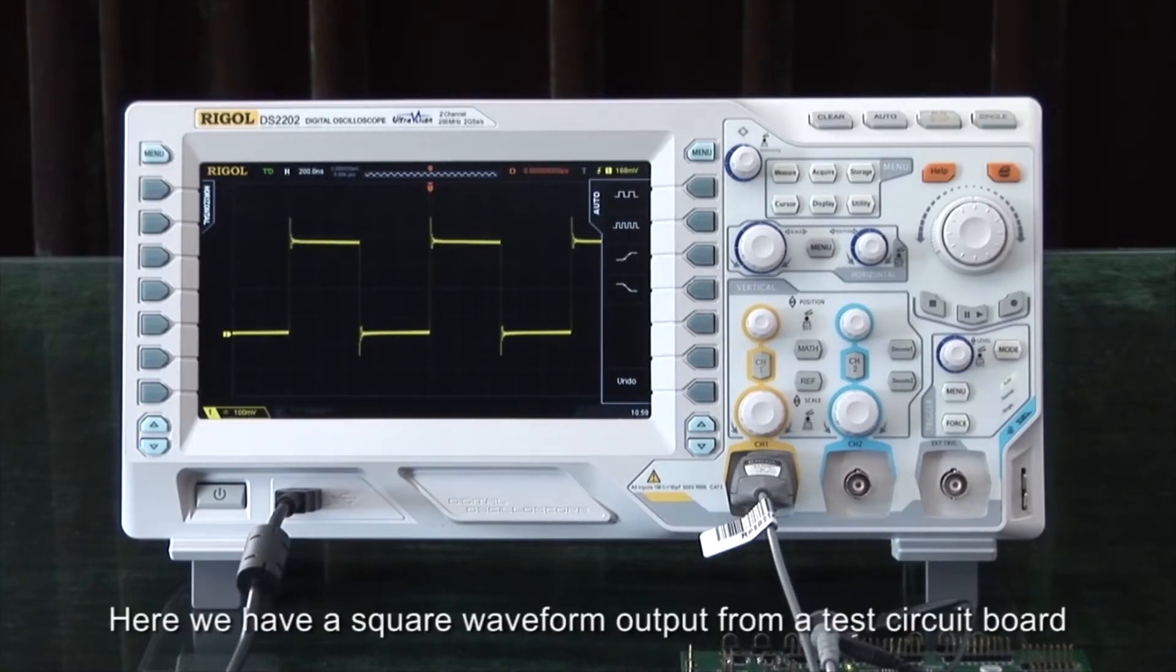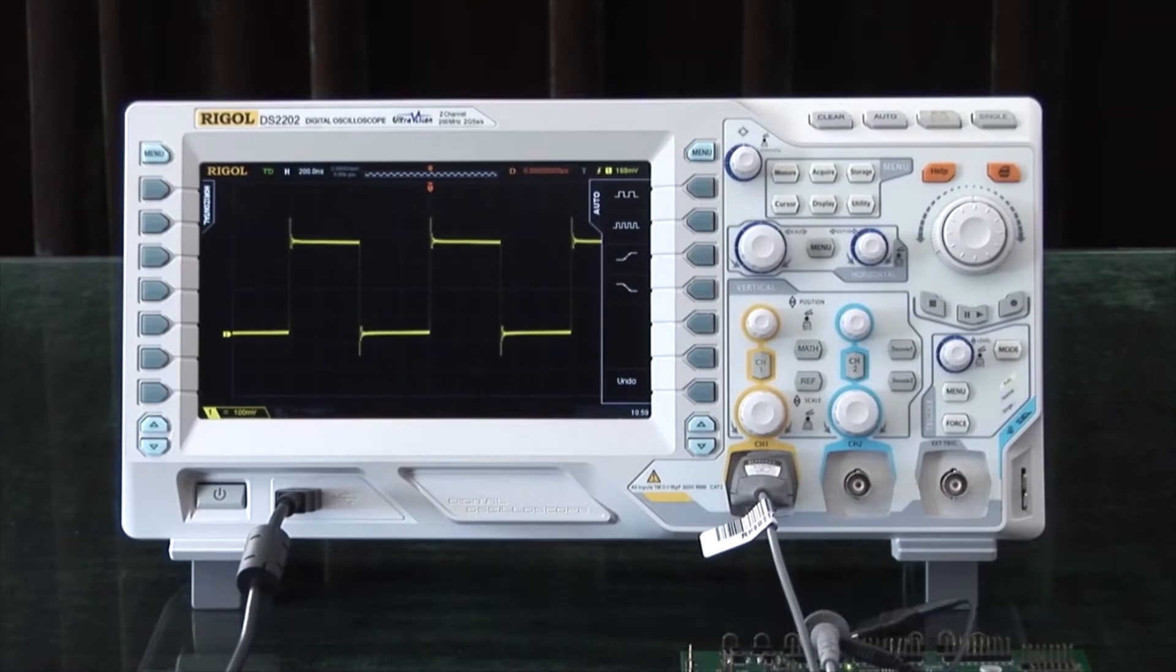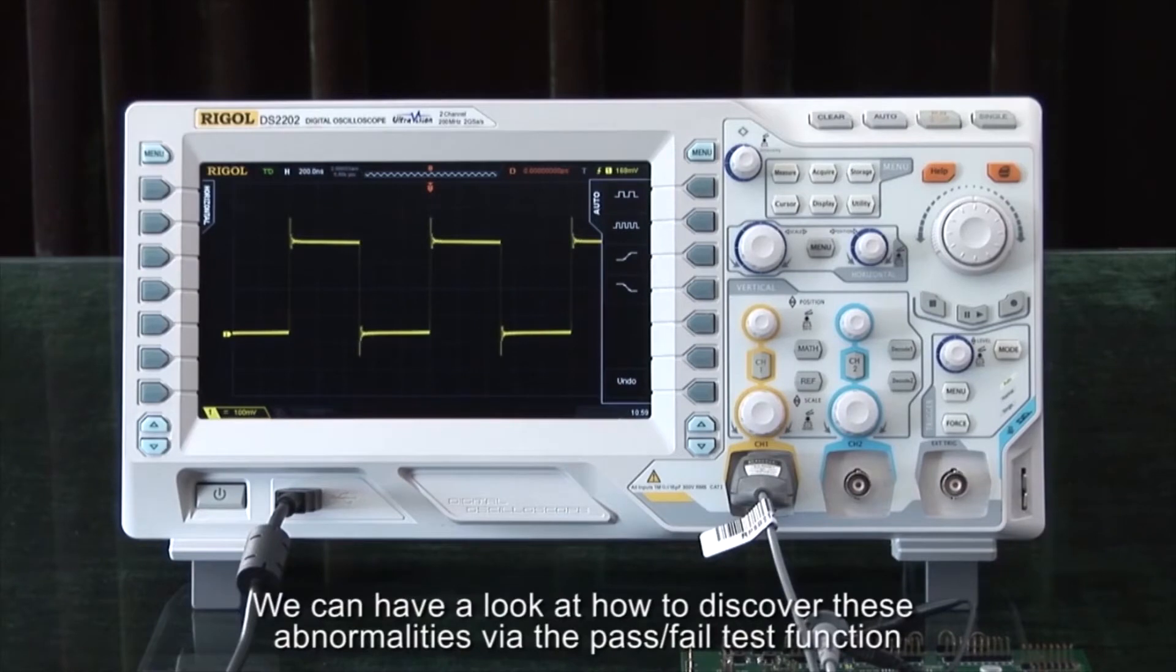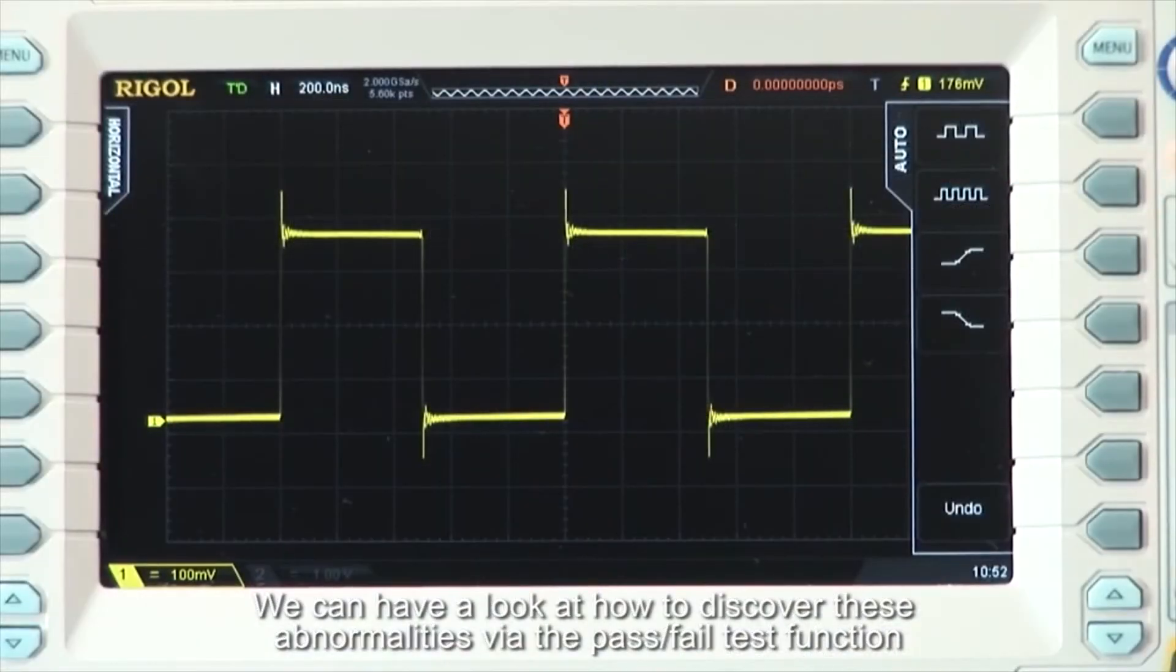Here we have a square waveform output from a test circuit board. It features an abnormality every 100,000 periods. We can see how to discover these abnormalities using the pass-fail test function.